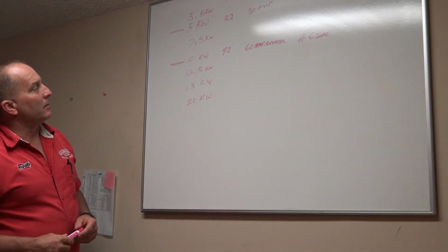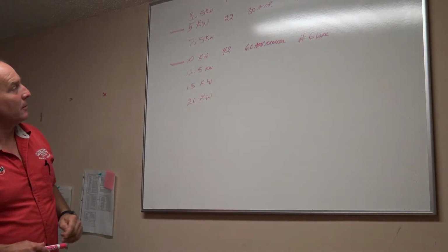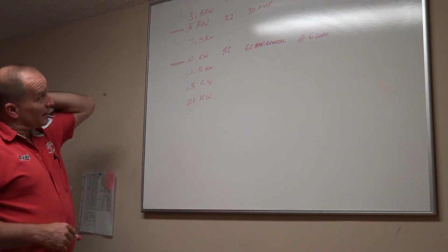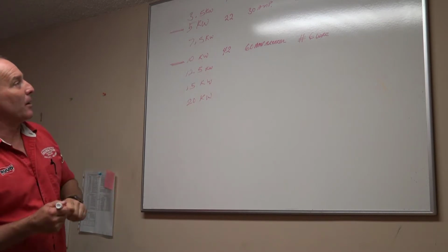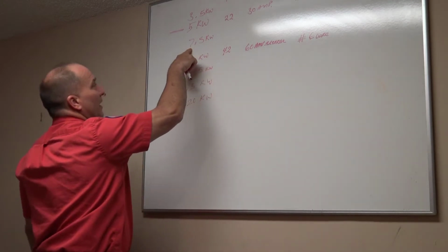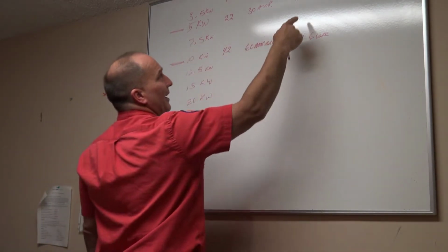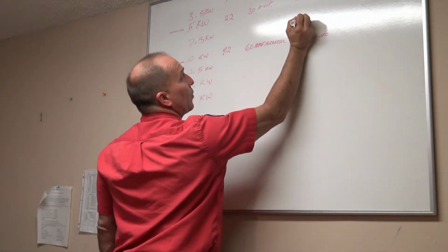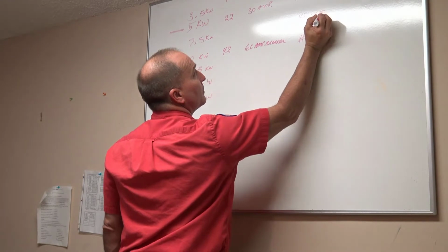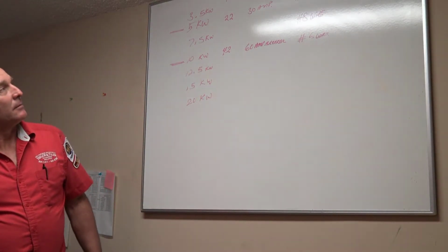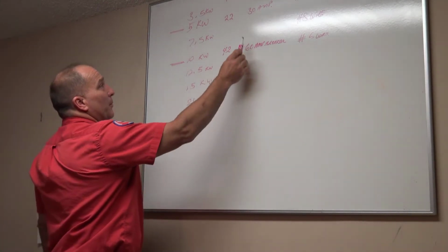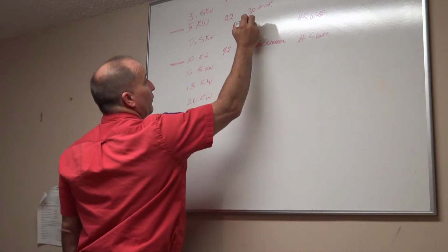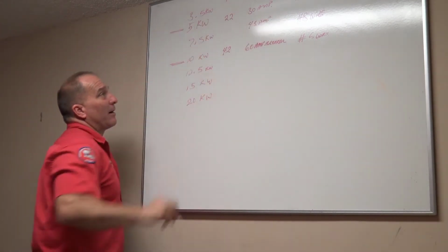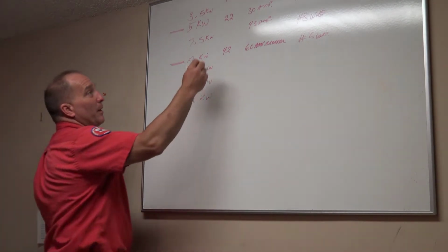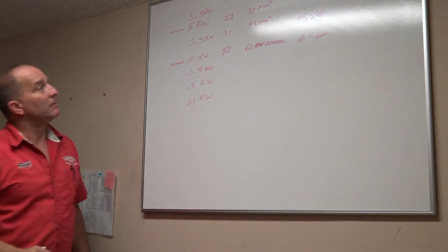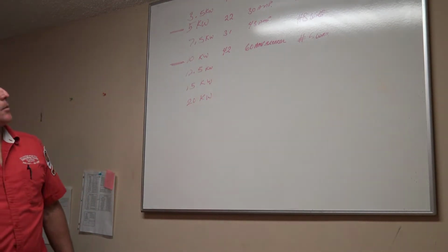Okay, I'm going to jump this all the way up to 20 kW. Well, let's continue down. Let's actually make this kind of in the middle of all this here. Let's go in the middle. I've got a number 6 wire with 10 kW heat, and I'm at 7.5 now. I've got a 10 wire here and a 6 wire here. How about if I stick a number 8 wire on 7.5 kW? Can we do that? Well, between a 60 amp breaker and a 30 amp breaker, what if I put a 45 amp breaker for 7.5 kW? What if I go in the middle and call it 31 amps? Am I okay? Yeah, I'm okay.